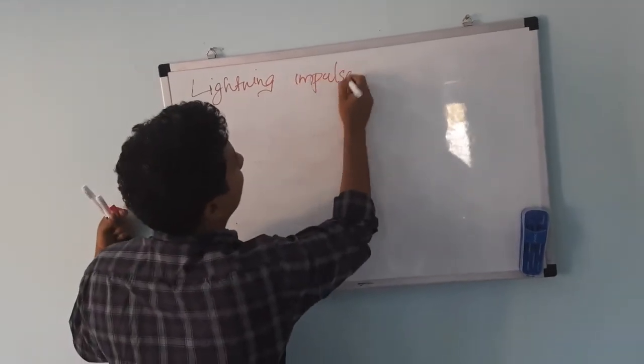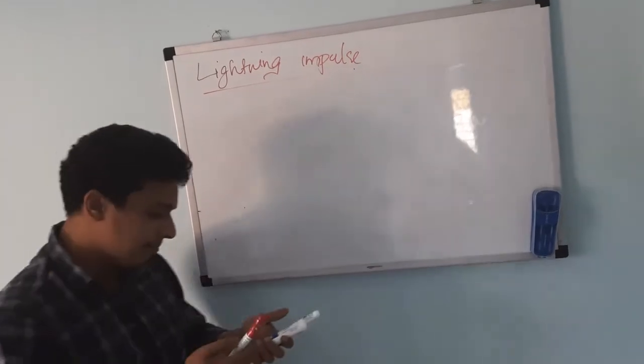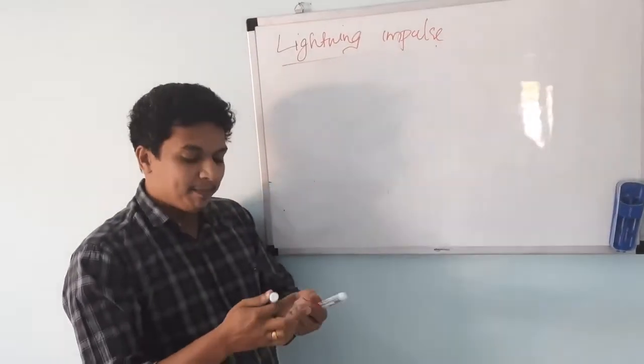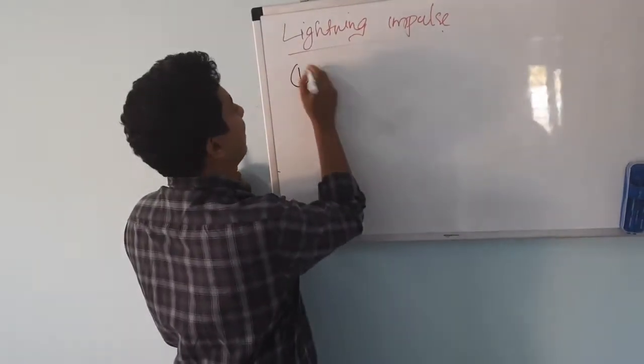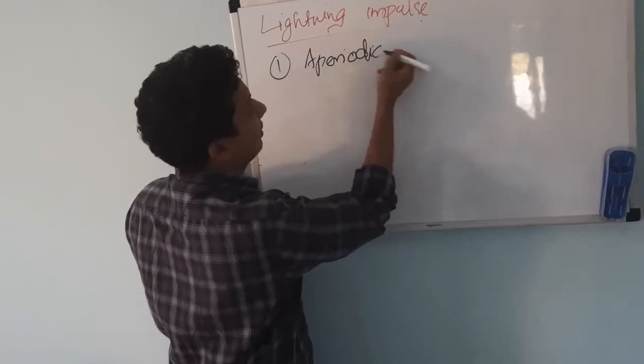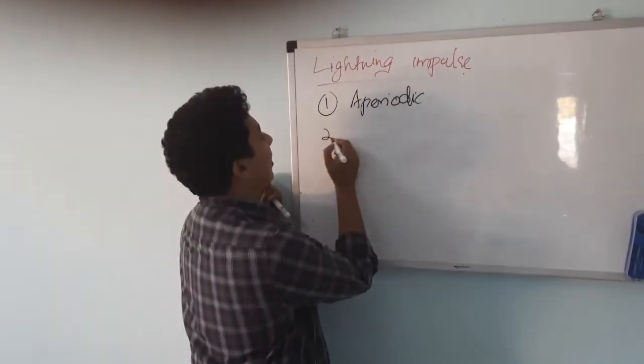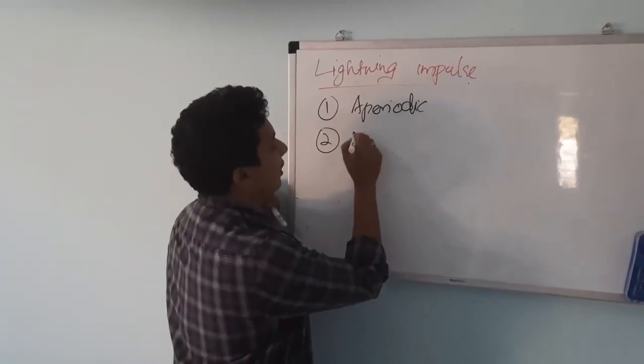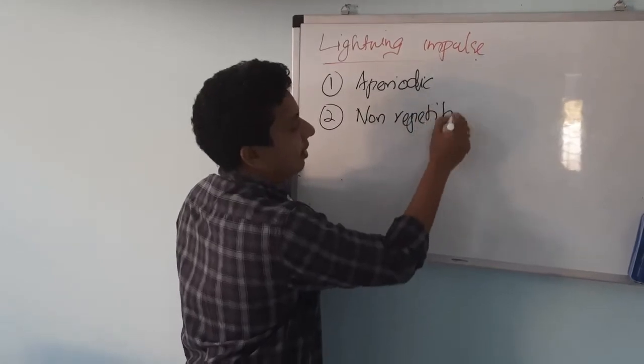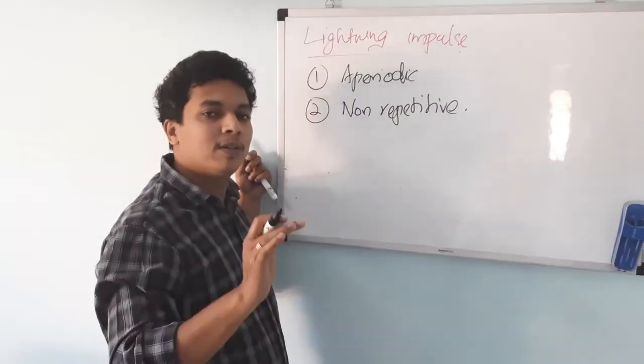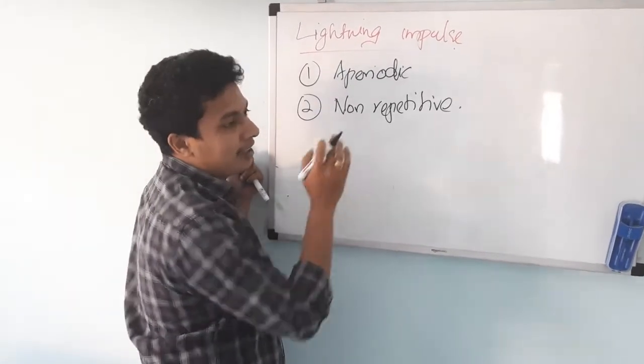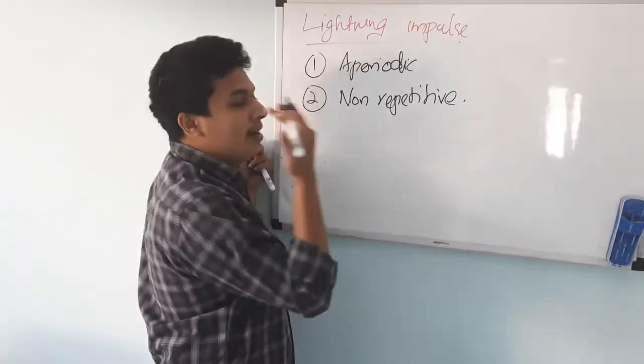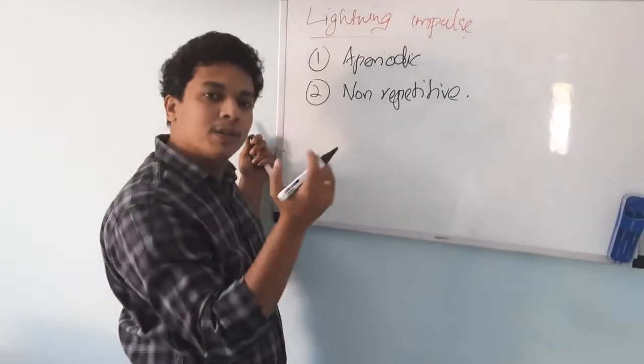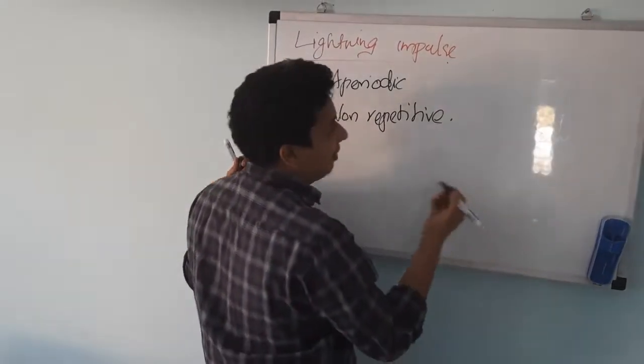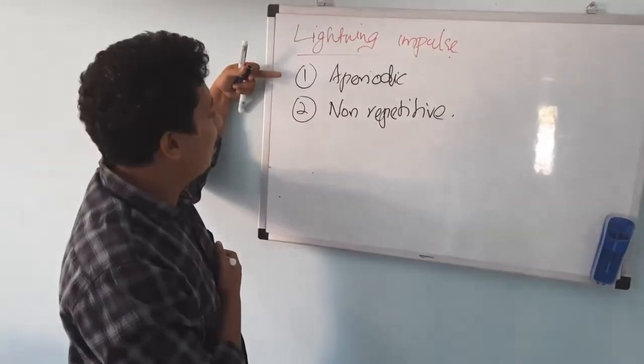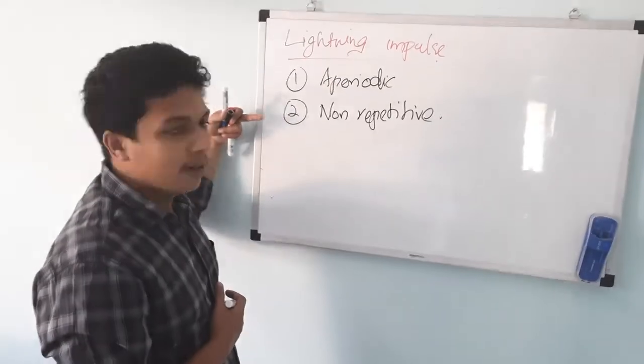Lightning impulse - the main interesting part is that your lightning impulse voltage is aperiodic, meaning it is not a periodic signal like our sine wave. The second point is that it is non-repetitive - the same kind of impulse voltage is not going to occur again and again. So we have to keep this in mind when testing high voltage equipment; we cannot expect the exact same impulse voltage to occur again. That's why usually you have a threshold for seeing that. So the main two things are: it is aperiodic, and it is non-repetitive.